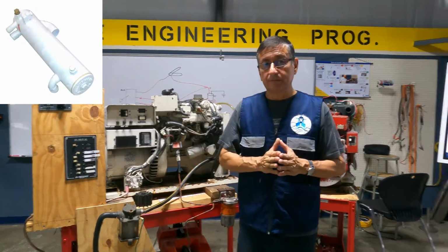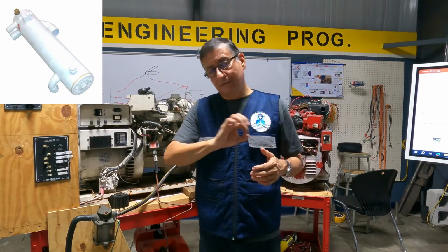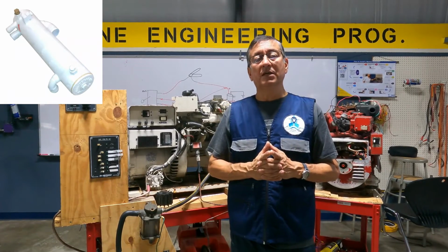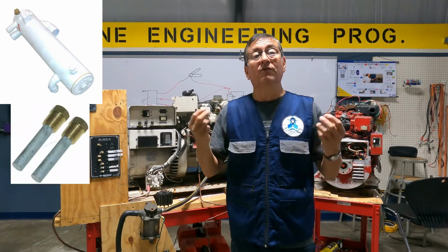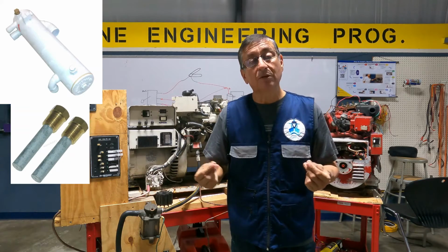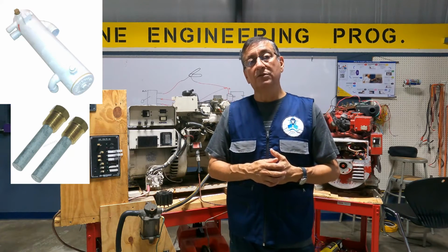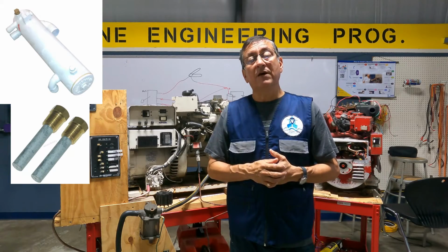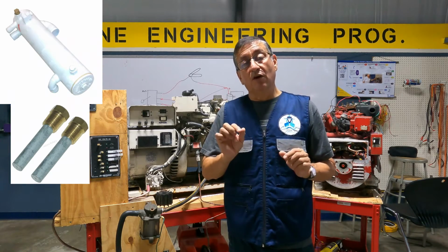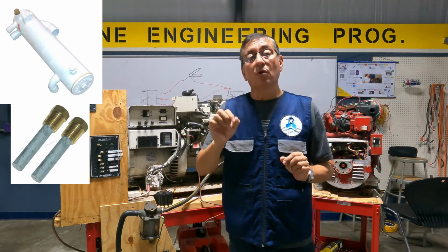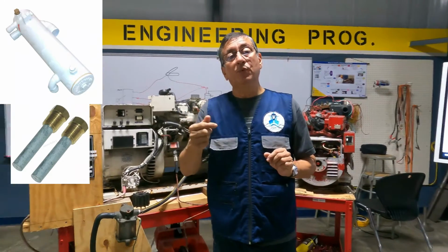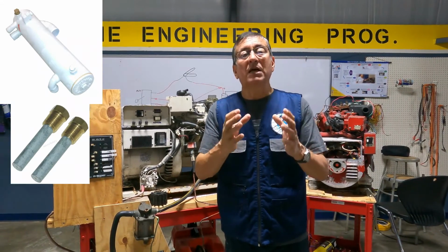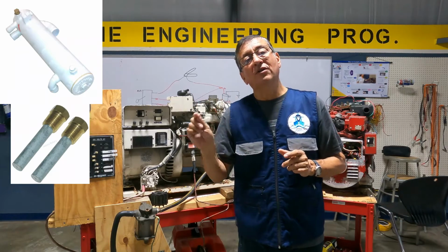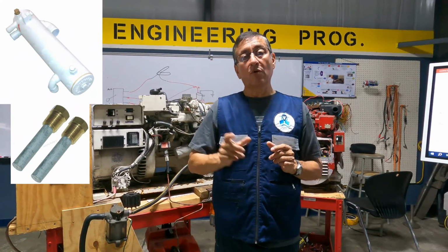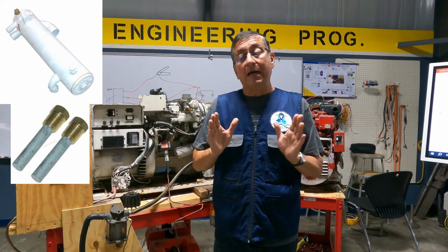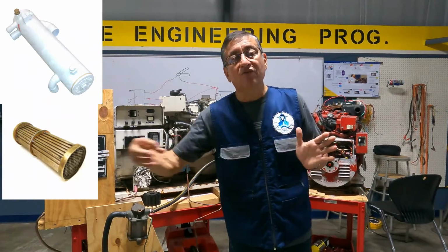Okay, in the heat exchanger, once again, copy the serial number of the heat exchanger, order a couple of extra anodes, pencil anodes, sacrificial anodes, and verify the position of the raw water input, raw water output, coolant input, coolant output. Understand the heat exchanger. Understand how the flow of coolant is, how the flow of raw water is. And don't forget, try to get an extra element of the heat exchanger.